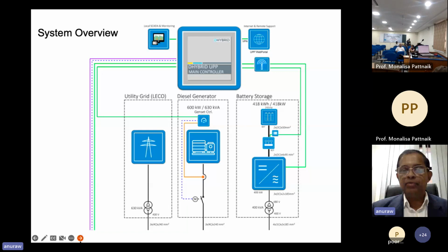For optimization, we can change the operating points. For example, when the battery should stop discharging, whether at 20% SOC or 30%, looking at battery health and current literature on lithium-ion batteries, we can change them for longer life on one hand, and on the other hand, get maximum use of energy storage to meet our demand when and where required.